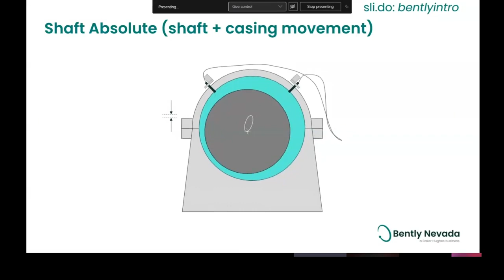But by combining those technologies, by taking that velometer signal, you integrate it to displacement, and you relate it to that proximity probe. They need to be mounted in the same plane and compared to each other. But by comparing that velometer signal to the actual proximity probe signal, we can now get a sense of how the shaft is moving completely independent of that bearing housing. This is generally going to be for larger machines with a very large shaft, and relative to the size of the shaft, the bearing housing just can't be big enough to damp out or to eliminate the bearing housing movement.